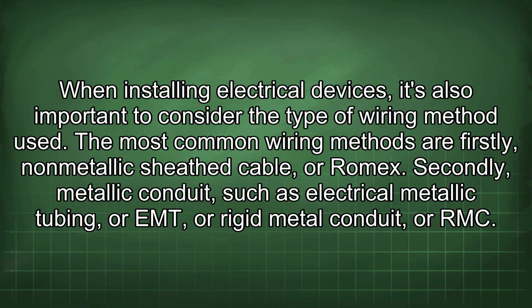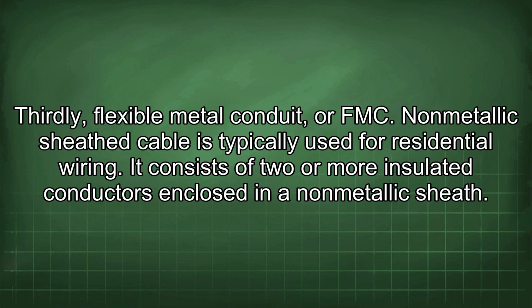When installing electrical devices, it's also important to consider the type of wiring method used. The most common wiring methods are firstly, non-metallic sheath cable, or Romex. Secondly, metallic conduit, such as electrical metallic tubing, or EMT, or rigid metal conduit, or RMC. Thirdly, flexible metal conduit, or FMC. Non-metallic sheath cable is typically used for residential wiring. It consists of 2 or more insulated conductors enclosed in a non-metallic sheath.